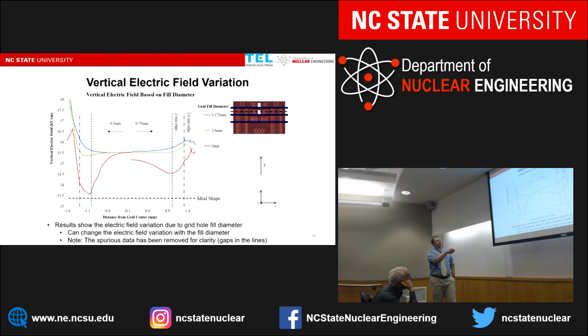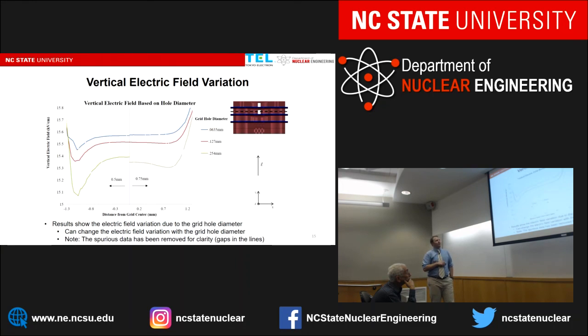As you can see, we get some differences at the 2 locations as well as radially across the probe. One, you see this huge discontinuity at 2 millimeters, and there's a slight discontinuity at the 3.75 millimeters. But again, we want just a straight line. So these are showing that the electric field is changing depending on what portion you're above. And you also see these drastic changes in the shape on the edges, which again we don't want, and what we saw earlier, and we just want a straight line. And so in this instance, 2.6 is giving the closest, most uniform field above the third grid, as it is straight across the 2 portions here, and it's pretty flat across the whole fill diameter.